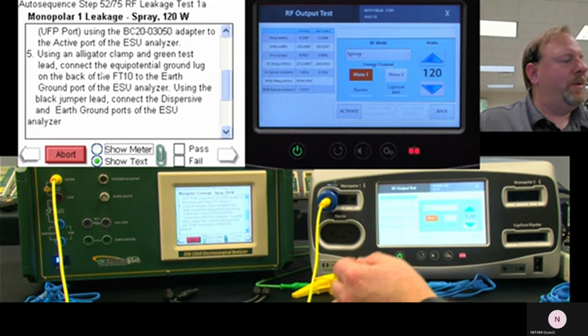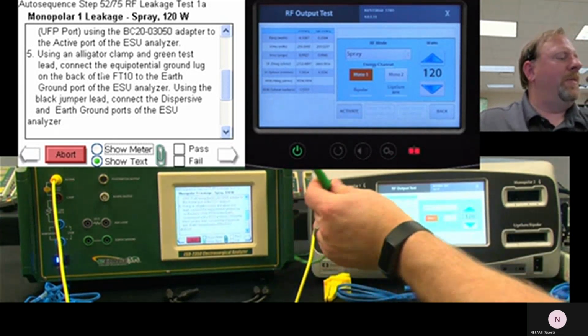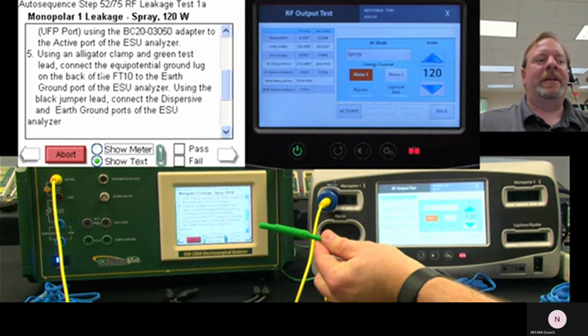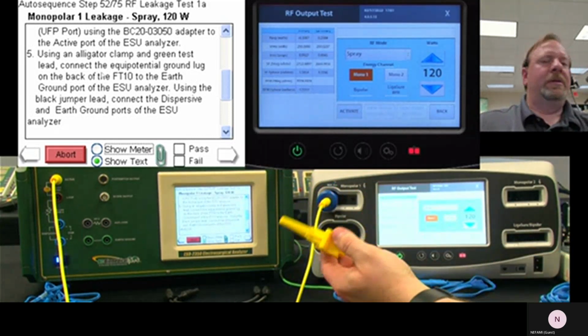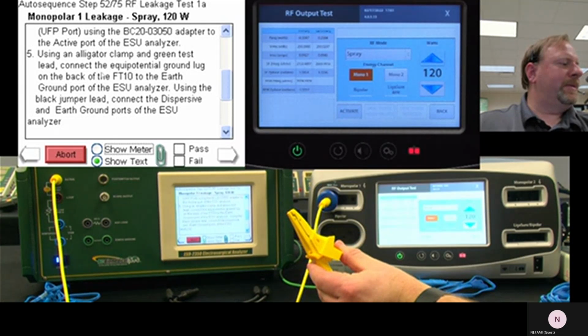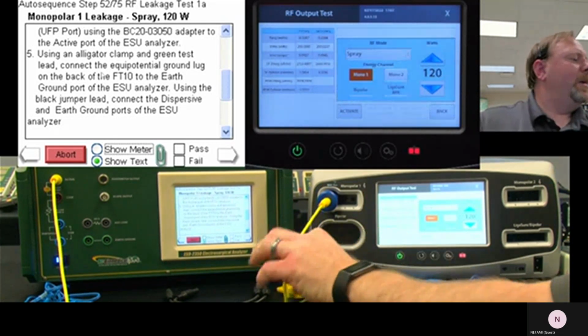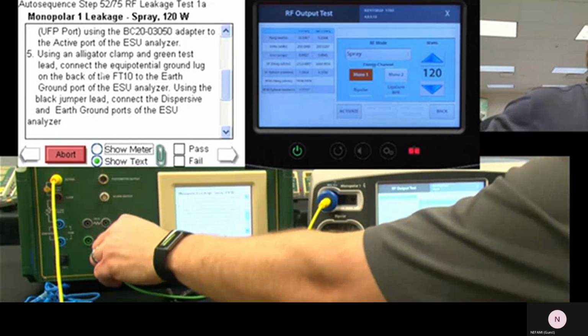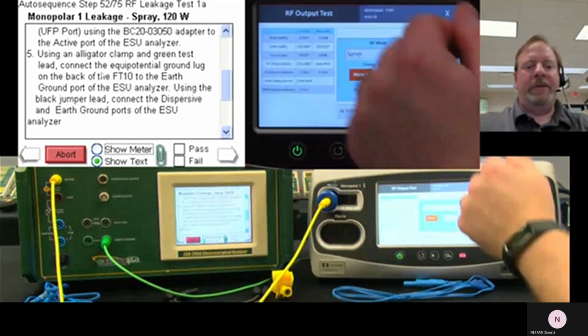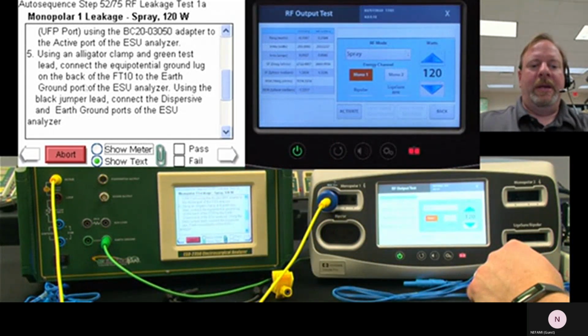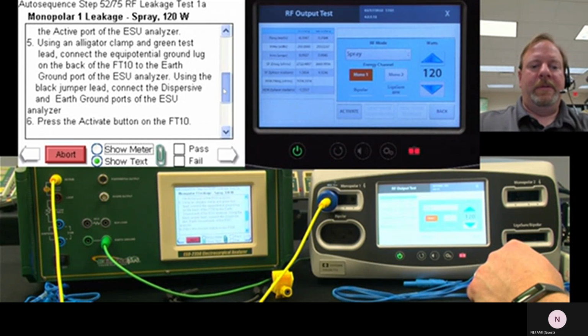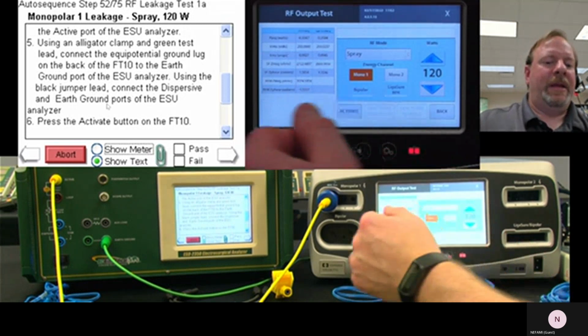So alligator clamp between the green. So on the back of the generator, I have this connected to an alligator clamp. It does come with the accessory kit. And that's on the ground lug on the back of the generator for the service manual. And then earth ground. Okay, so then it says connect the equipotential lug to the back of the earth ground of the ESU analyzer using the black jumper lead. Connect the dispersive and ground.